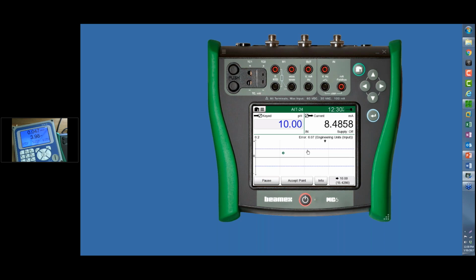And now that we know what our 10 is, we know which vial. So here's my 10 pH I'm going to put in here. And unfortunately, I don't have a way to show you guys what I'm doing here, but I'm going to lift out this probe and I'll put it into the water, and then I'll rinse it out. Should have Ned give us some feedback here while we're doing this. So I'm just swapping these out right here. So I just need to rinse out that probe, and I've got my 10 pH solution in here. Good, rinsing, rinsing, rinsing. And here we go.